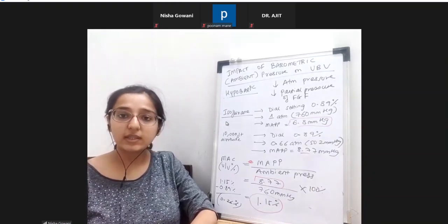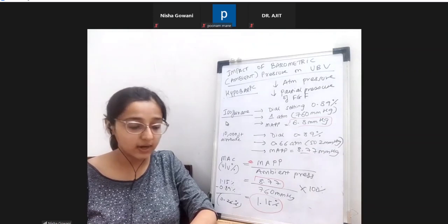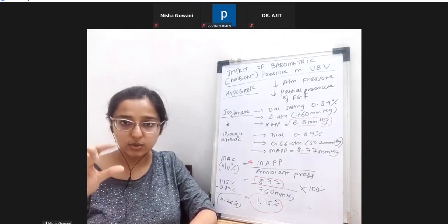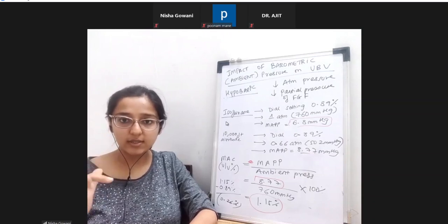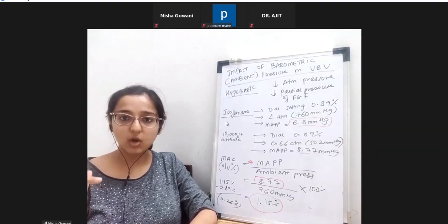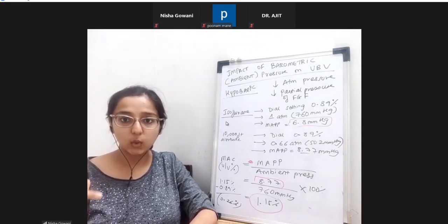Then overfilling. Sometimes overfilling can occur, right? That will happen when you are not able to see the sight glass, through which you know the level of the liquid agent. If that glass is not there or not working properly, you might overfill.